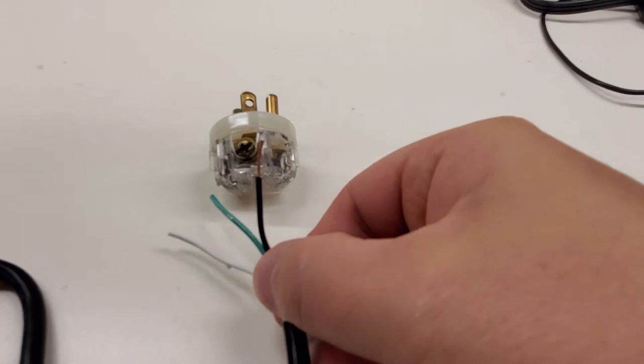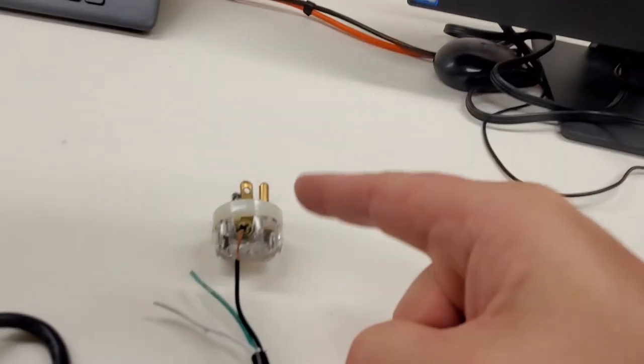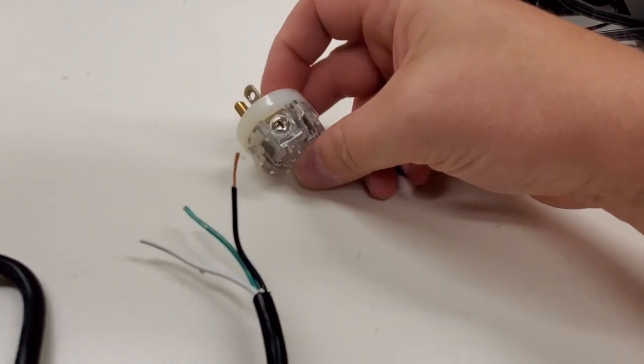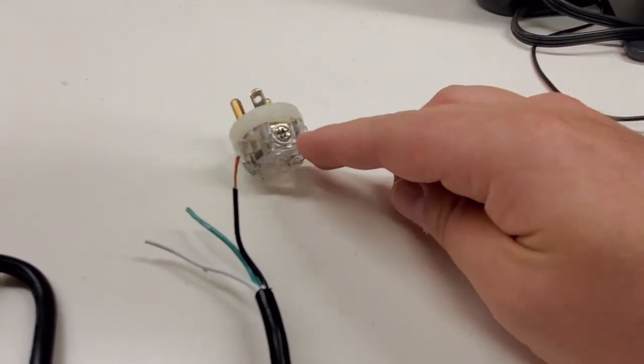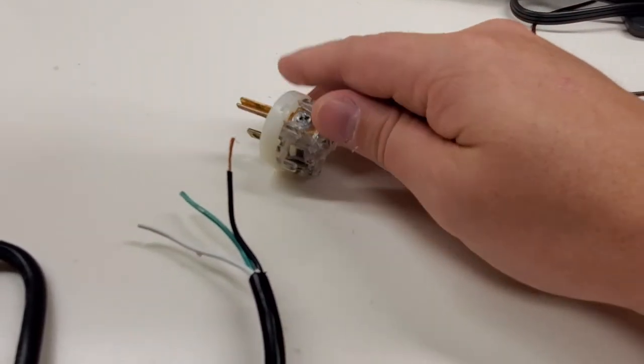Point being, when aligning up the wires, black to brass or it's your ass. Always put black on the brass screw. Neutral goes on the silvery screw, which is probably nickel plated. And ground always goes to the ground lug.